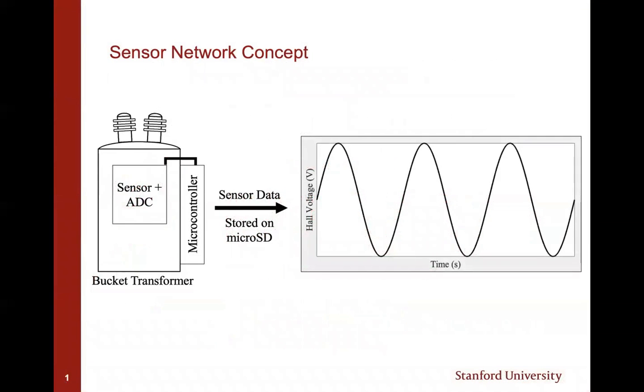Transformer cores produce powerful AC magnetic fields, which can be used to monitor transformer health and performance. However, the inside of a bucket transformer is a harsh environment for sensors. Temperatures reach as high as 140 Celsius, and shorts can produce magnetic flux of 2.5 Tesla for 3 seconds. Normal field strength is highly variable, between 5 and 300 millitesla. In order to capture meaningful data, sensors in the bucket must have resolution better than 5 millitesla, while remaining unaffected by temperature or very high flux.